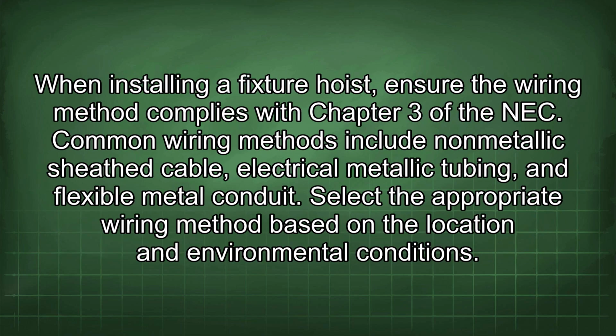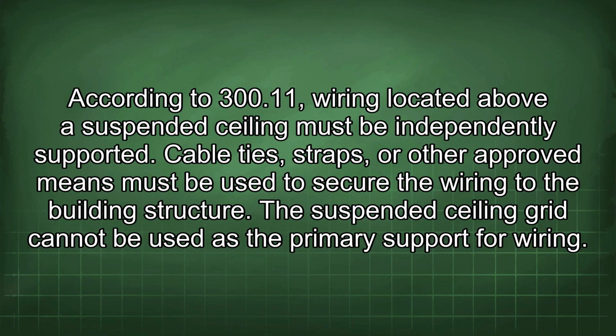When installing a fixture hoist, ensure the wiring method complies with Chapter 3 of the NEC. Common wiring methods include non-metallic sheathed cable, electrical metallic tubing, and flexible metal conduit. Select the appropriate wiring method based on the location and environmental conditions. According to 300.11, wiring located above a suspended ceiling must be independently supported. Cable ties, straps, or other approved means must be used to secure the wiring to the building structure. The suspended ceiling grid cannot be used as the primary support for wiring.